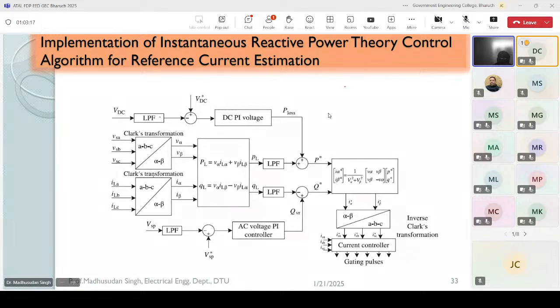So you need to sense the actual DC voltage, compare with reference using a PI controller. This will be added to real power, and similarly for AC side voltage also you need to sense the peak of AC side, compare with the desired peak, and then this controller will create the appropriate component of reactive power, which will be added into the reactive power demand.